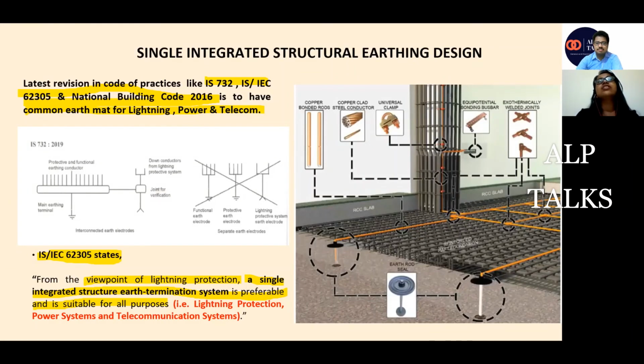Now, there is a question people generally ask me: whether we can combine the earthing for the lightning protection system with power and telecom or not. I want to give this reference: as per IS 732, as per IEC 62305, and as per the National Building Code, we can have a common earthing for lightning, power, and telecom, if I am designing the earthing properly, with step potential, touch potential, and ground potential rise satisfied, and resistance less than 1 ohm. So I can combine the earthing.